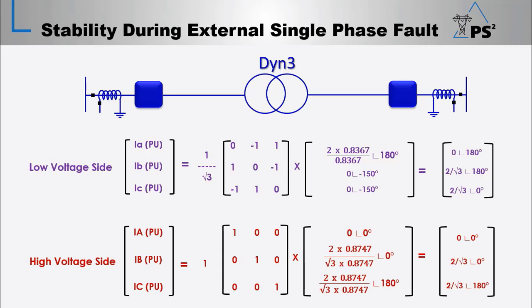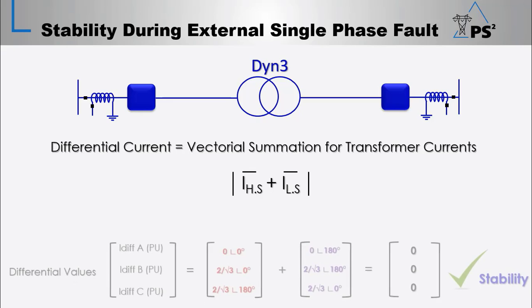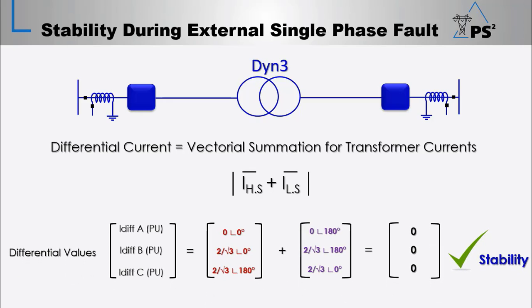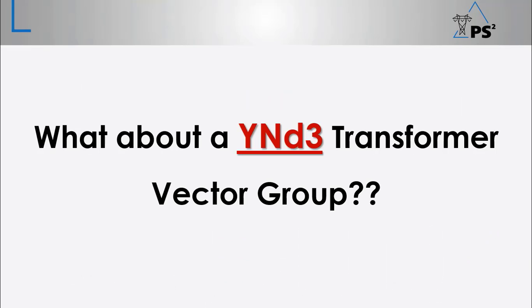Then by substituting the current value in the per unit equation, we would get the per unit currents with 0, 2 over root 3 angle 0 degrees, and 2 over root 3 angle 180 degrees. Then the differential current would be 0, which indicates a stability condition. Now it's the time for a tricky point. What about the YND3 transformer vector group?